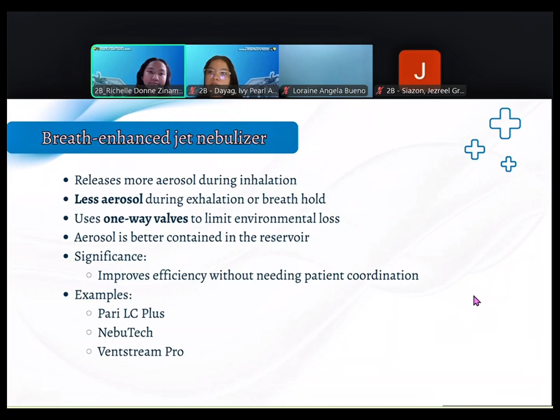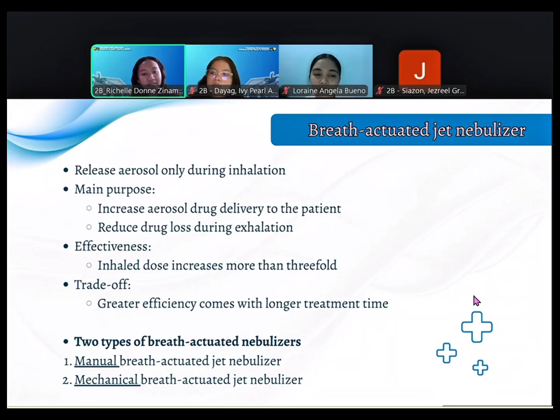Last is the breath-actuated jet nebulizer. This releases aerosol only during inhalation, and it has two main purposes: to increase aerosol drug delivery to the patient and reduce drug loss during exhalation. Its effectiveness is that the inhaled dose increases more than threefold. Its trade-off is that greater efficiency comes with longer treatment time. Under the breath-actuated jet nebulizer, there are two types, the manual and the mechanical. To further explain, next slide please.